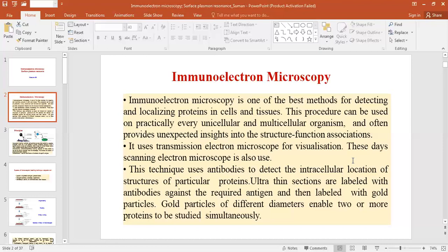So in the transmission electron microscope, electrons serve as a pseudo light source. High energy electrons emitted from the filament are accelerated and forced by electromagnets into a very fine coherent beam in the center of the microscope column. And because electrons are used, the microscope column and specimen area are maintained in a vacuum condition to prevent the deflection of electrons by atmospheric gases.